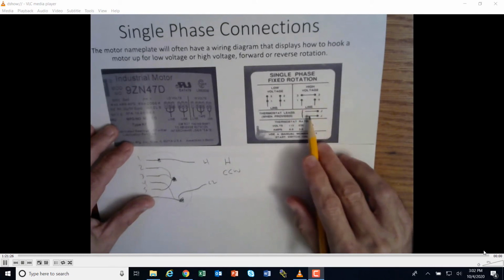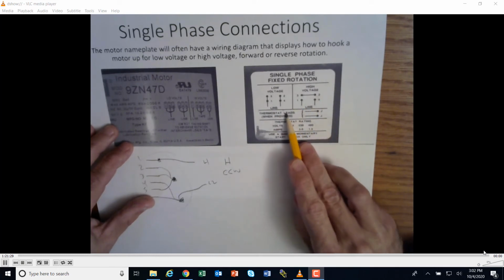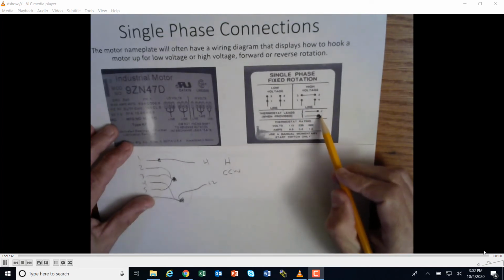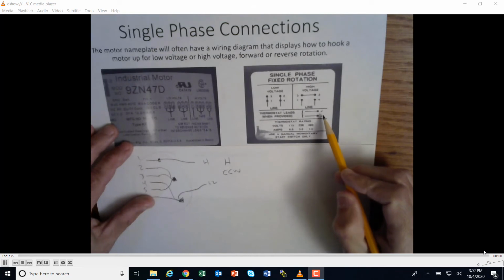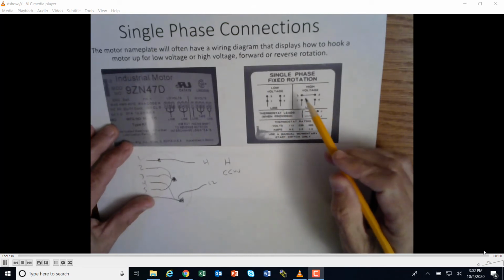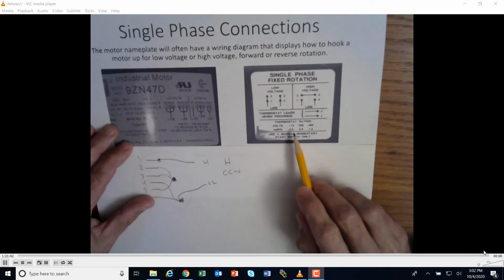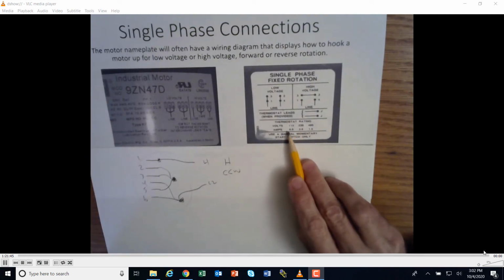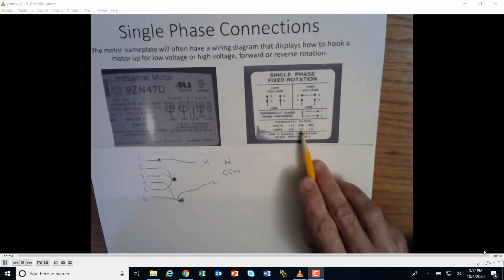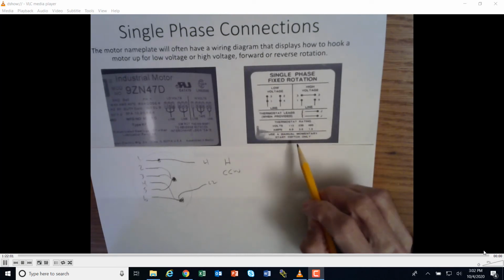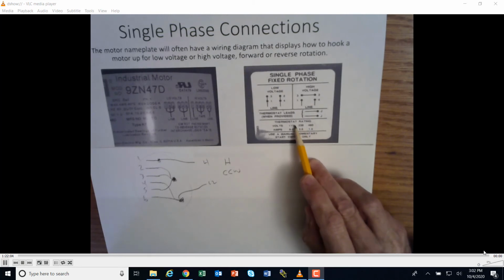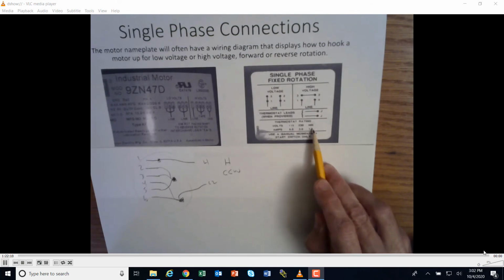But if we wanted to see what else was going on here, this has a thermostat lead, so they were provided so that we could connect these 2 leads and it would have a thermostat. There'd be some type of thermal protection on this motor if it ran too many amps. Okay, and the thermostat rating here is giving us how many volts and amps. So the motor is probably designed to pull about this many amps. If you exceeded this many amps, then the overload would trip, the thermostat would trip the motor. So I'm gonna guess that this is about a 230 volt 3 amp motor or a 115 volt 6 amp motor. Notice that these ratios are all the same. If you double the voltage, you cut the amps in half.